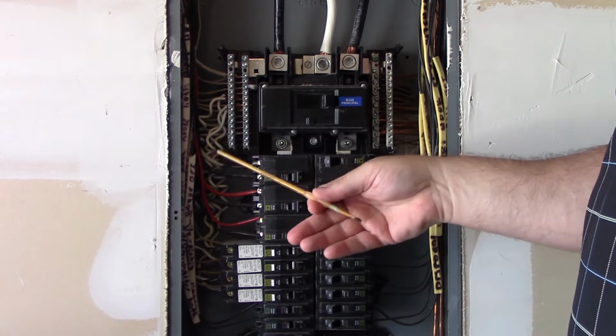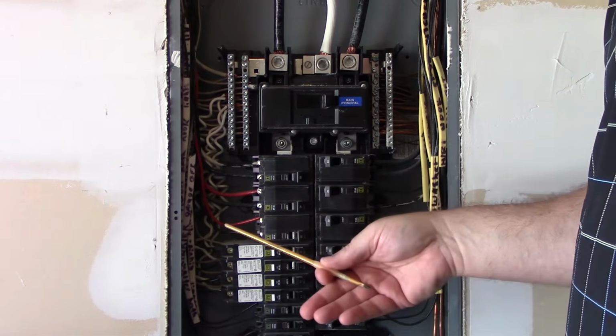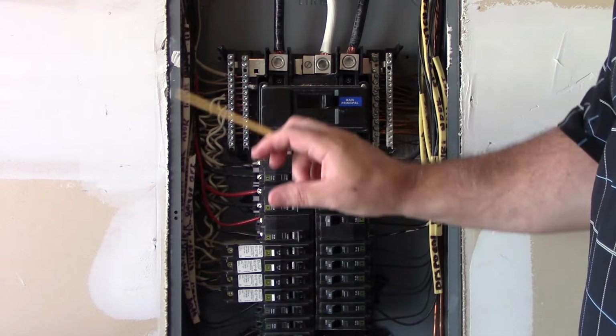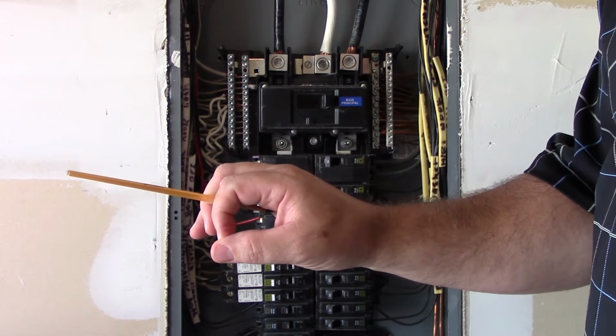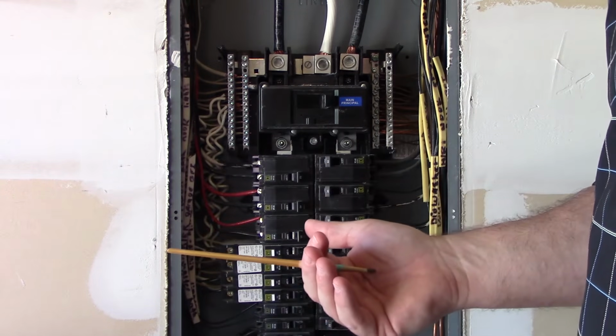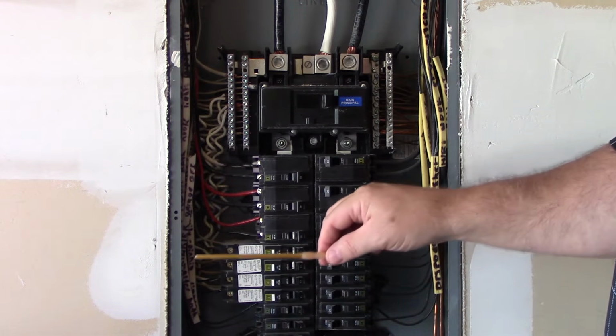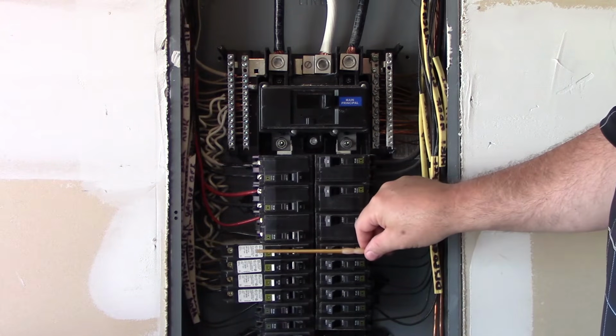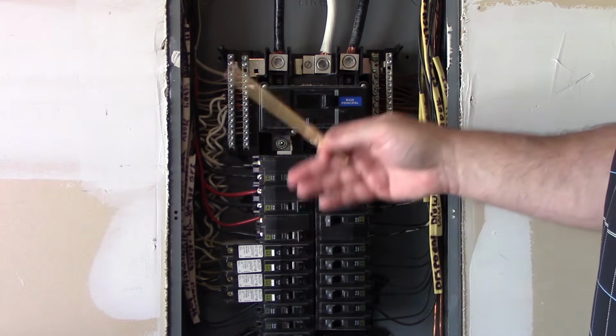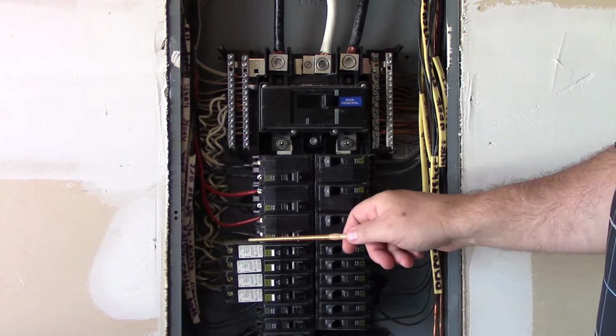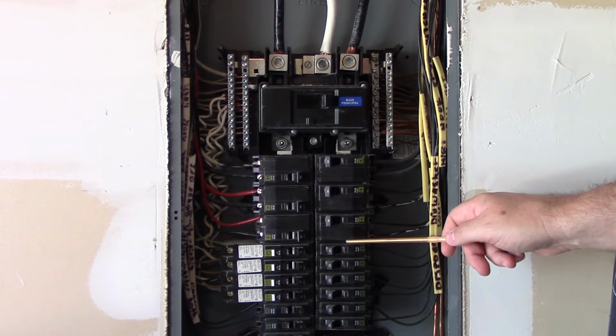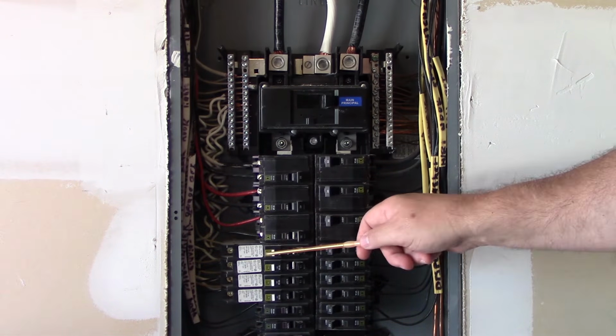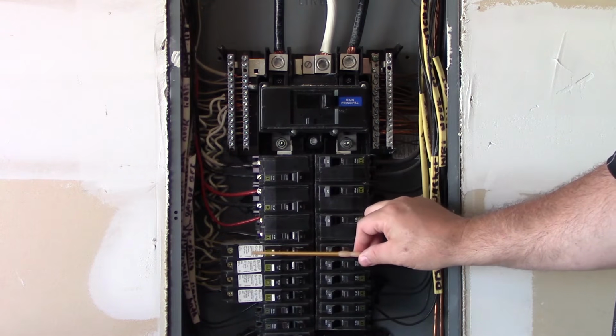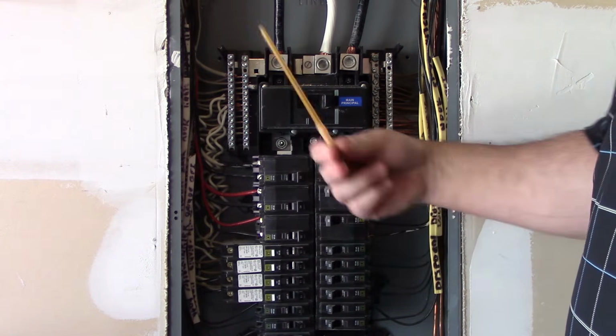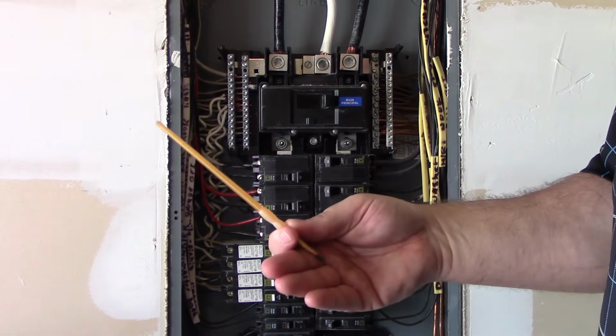So in a multi-wire branch circuit, if I've got 10 amps on A and 10 amps on B, then if it was properly installed, I'm going to have 0 traveling on the neutral conductor, the return conductor. There's a cancellation effect that takes place. But if I have both the black and the red on the A leg because they didn't use a two-pole breaker or two single poles with an identified handle tie, then I've got 10 amps on A and 10 amps on the other A because it's on the same line. What ends up happening is I have 20 amps traveling on that neutral because there's no cancellation effect.